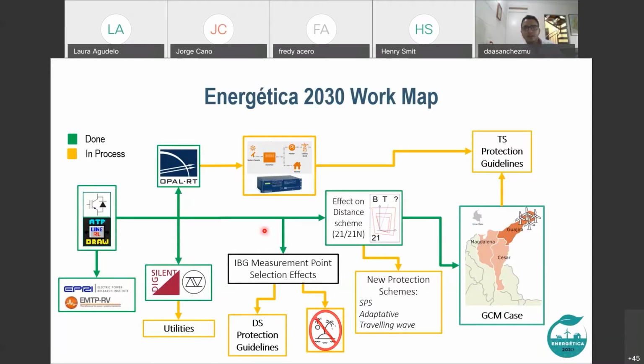And then we start to check several issues like the impact of IBG on distance protection schemes and the effect on the measurement point in the distribution system. Also, we are working on new protection schemes and on anti-islanding schemes. All of the above with the aim to establish what is the best practice when we have IBG resources in the distribution system and transmission system, and then establish protection guidelines for distribution system and for transmission system.